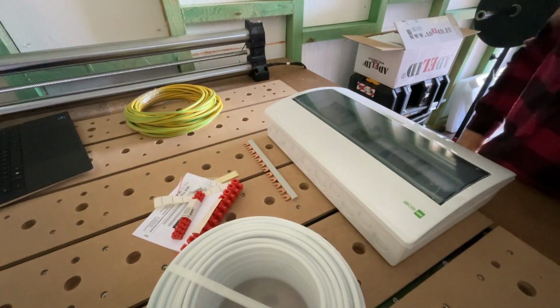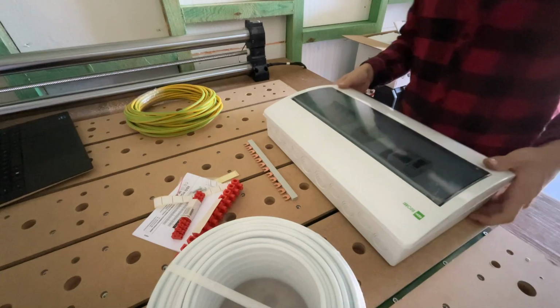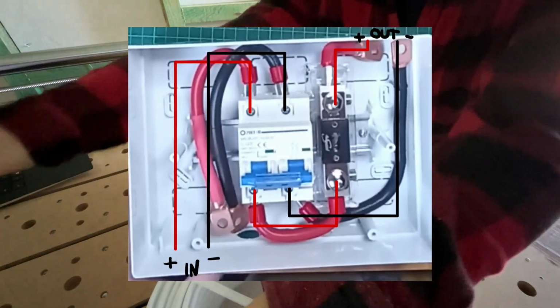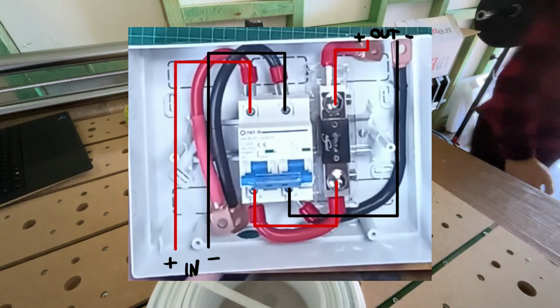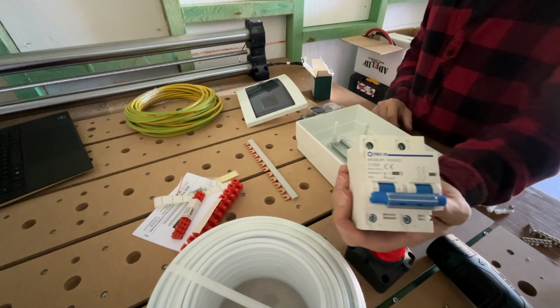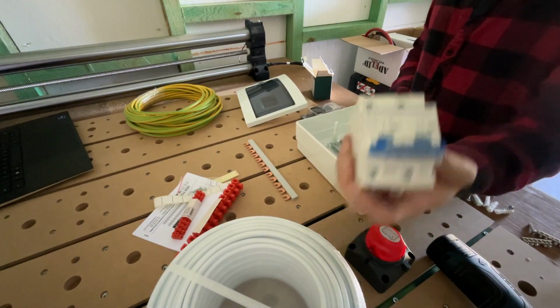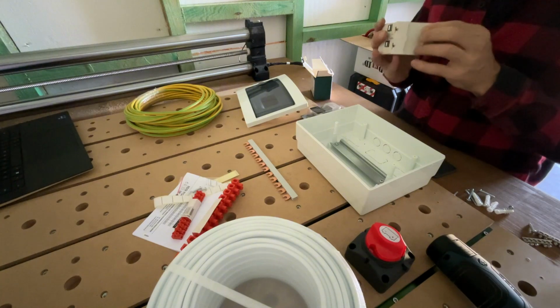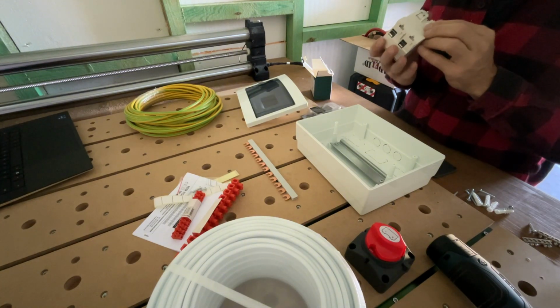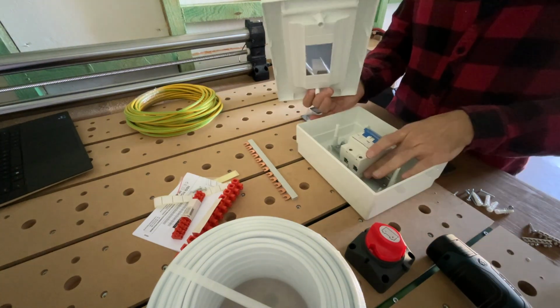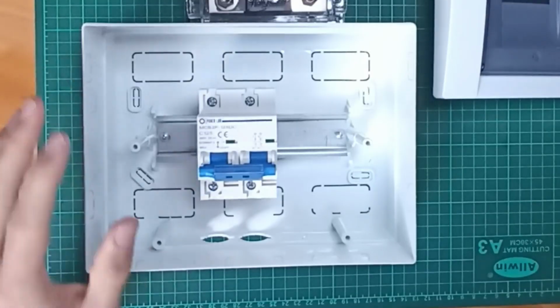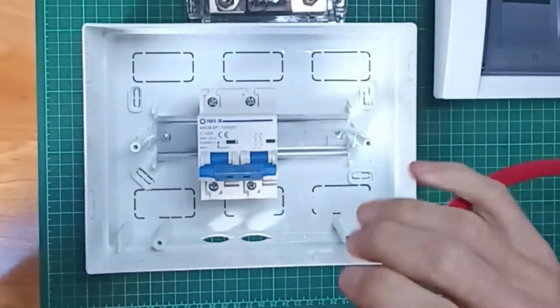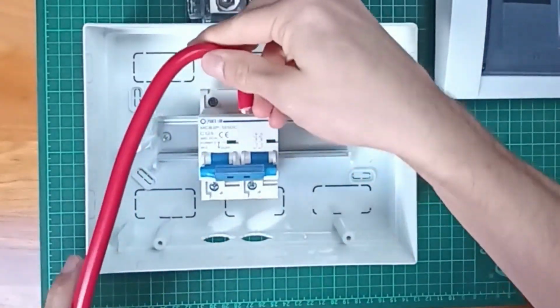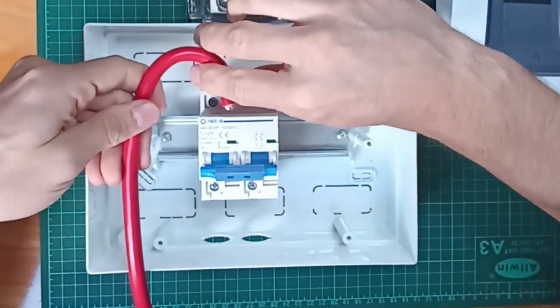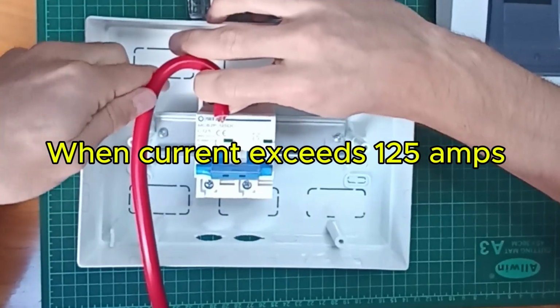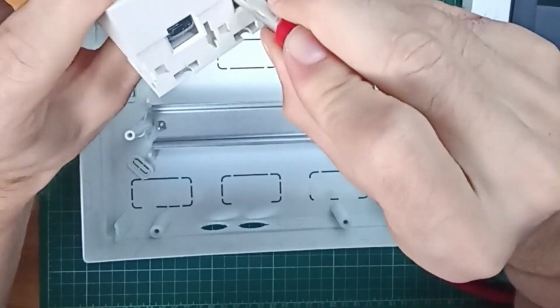First electric box done. Now we can move on to the power storage fuse box. This one is specific because there will be only 2 components. First one is a DC miniature circuit breaker, or MCB for short. This is a dedicated breaker for power storage units. This pretty complex device protects from overvoltage and mainly from overcurrent. Mine will break the circuit when current exceeds 125 amps.